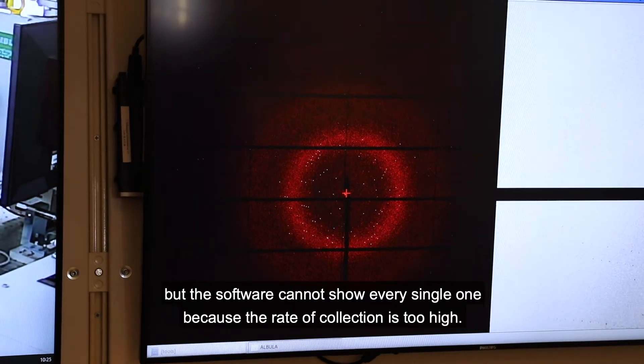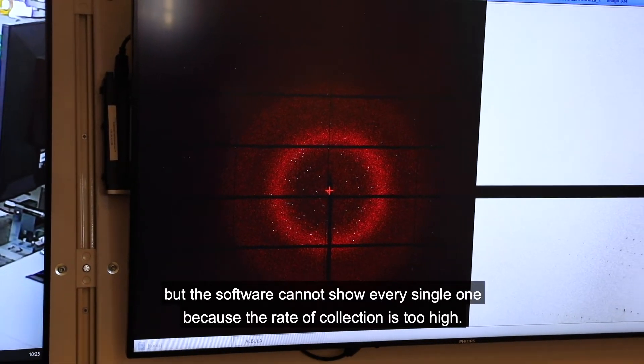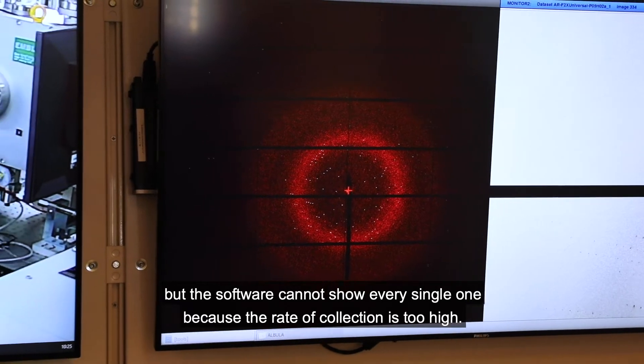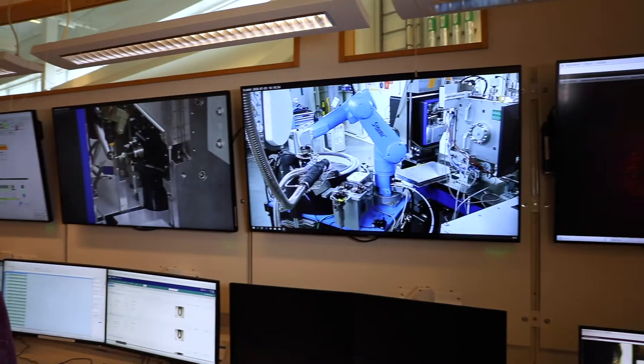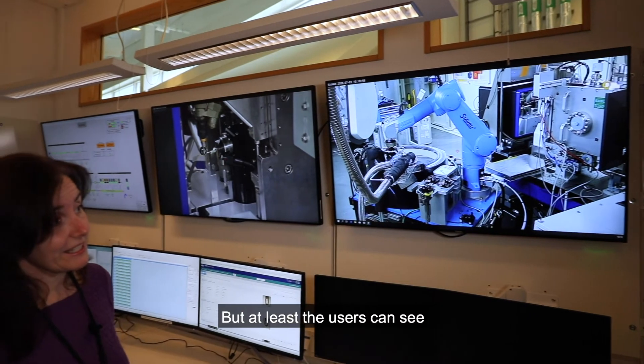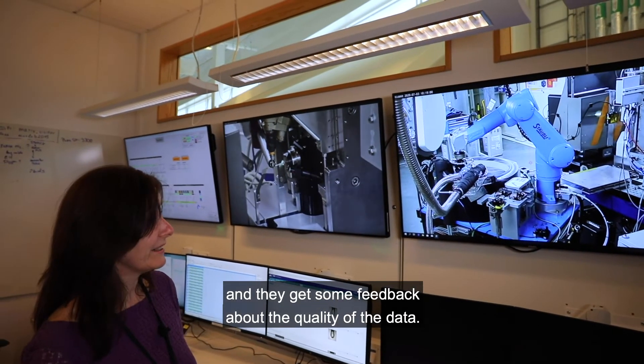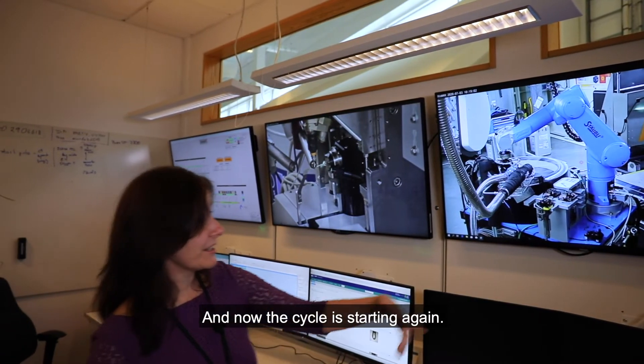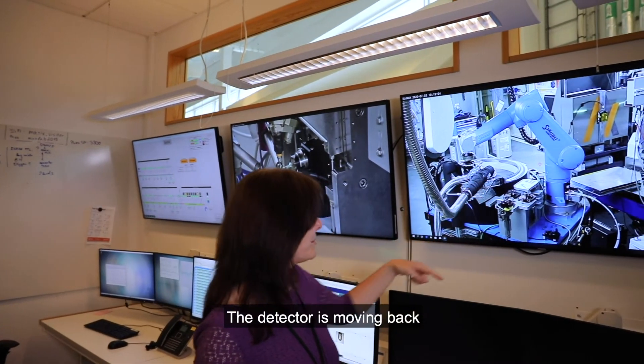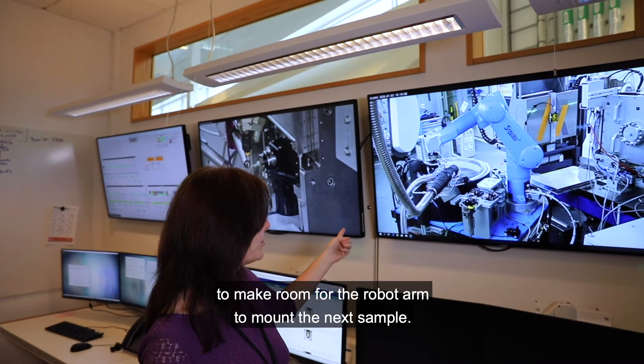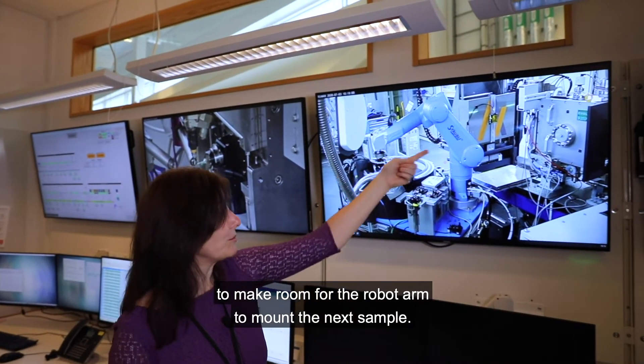But the software cannot show every single one because the rate of collection is too high. But at least the users can see, they get some feedback about the quality of the data. And now the cycle is starting again. So the detector is moving back to make room for the robot arm to mount the next sample.